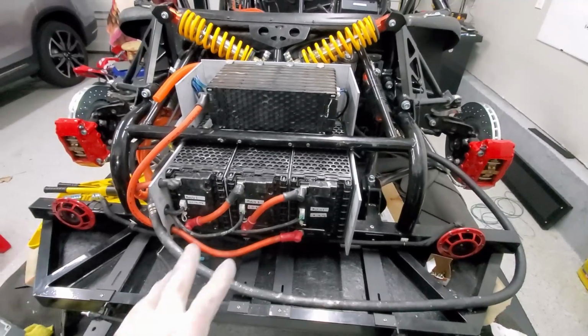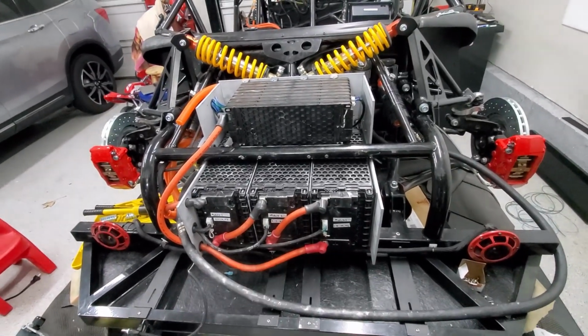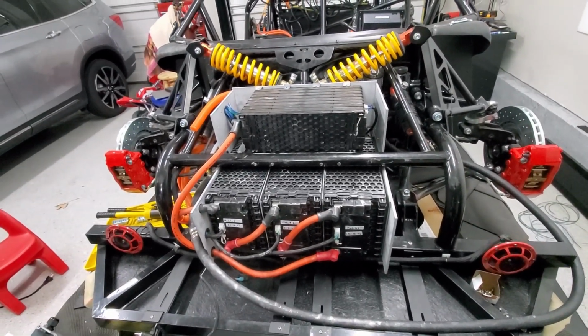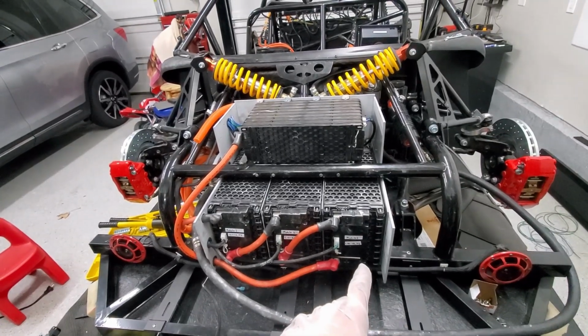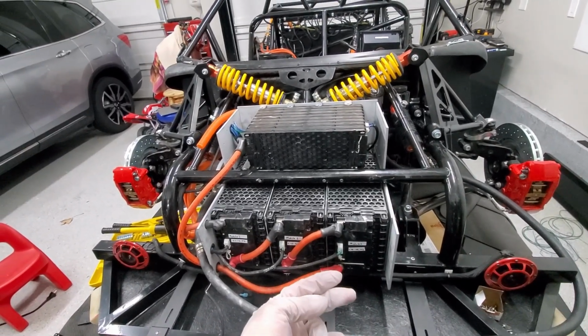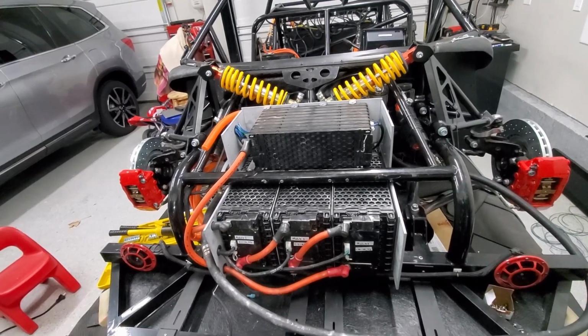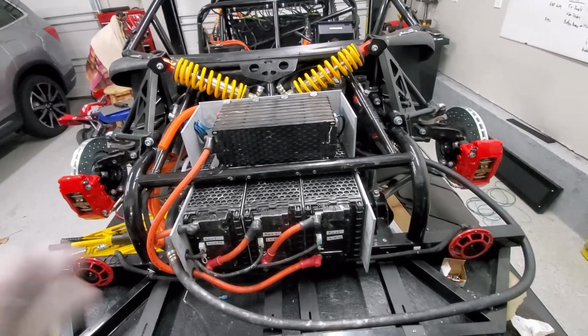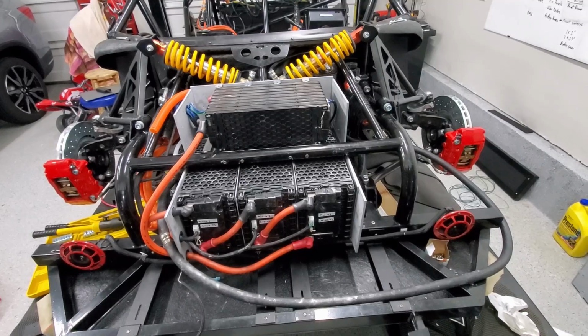All right, so I pulled the batteries off, had to take some of the cables off, got the pins, or essentially the thermistor wires, out of one slot and put them in the next slot. So we'll go ahead and fire up the BMS and see if we've got thermistor readings on all the cells now.